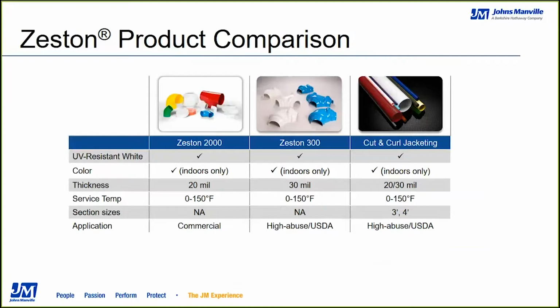Zeston 2000. This is our 20 mil offering. It is intended for fittings that will be both in hot water and cold water systems. The service temperature of the PVC itself is 0 to 150 degrees, but that doesn't mean it can't be used on a steam line. It just requires that the insulation be the proper thickness to reduce the temperature by the time it gets to the jacketing to less than 150 degrees.